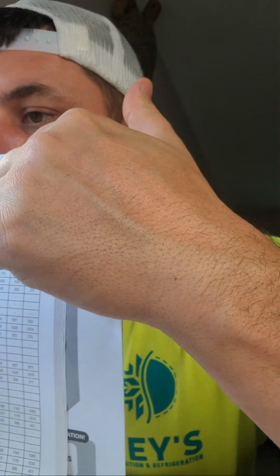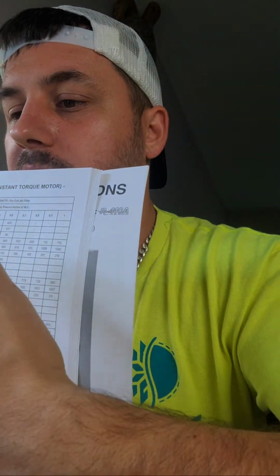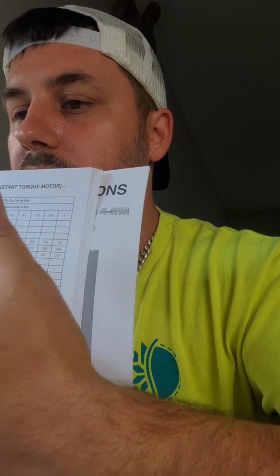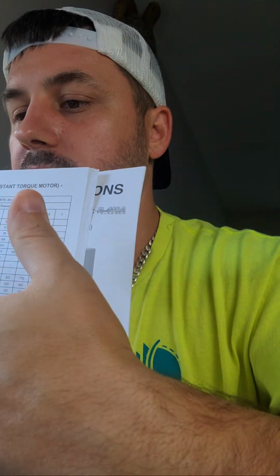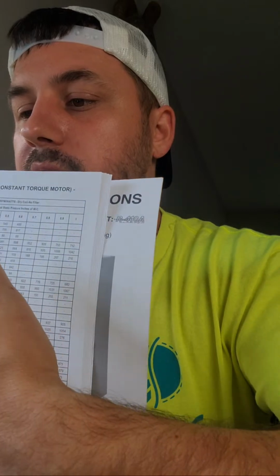What I did is I put a little orange mark on here, and it'll show you that at 0.5 inches of water column, you're going to get your most airflow. But anything below 0.5, you'll still get the same airflow because it's a constant torque motor. But anything above 0.5 up to 1 inch of water column, you're going to start reducing airflow. If you look, you can see that it goes up to 1 inch of water column, and then when you look at 0.5, you'll see that's the reason they have these dashes, because it's all going to be that number till it gets to 0.5, and then it starts dropping airflow as you go up in higher pressure. So anything in this area is where you're going to get your most airflow, and this is a 36. I don't know if y'all can see it, but it is a 36.